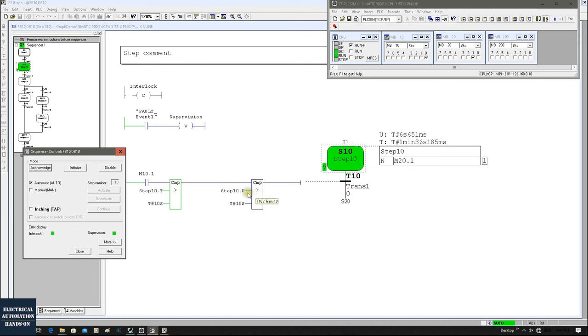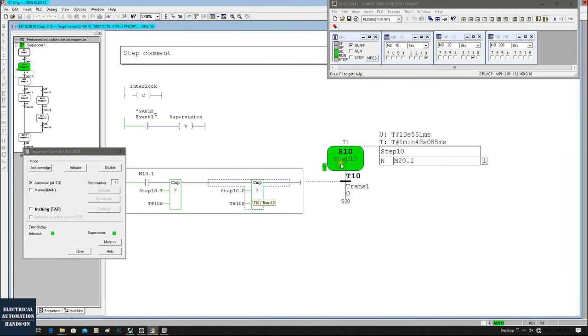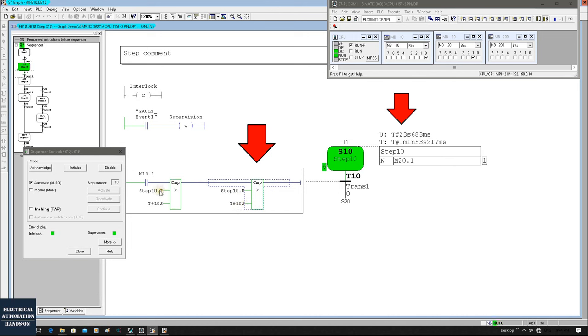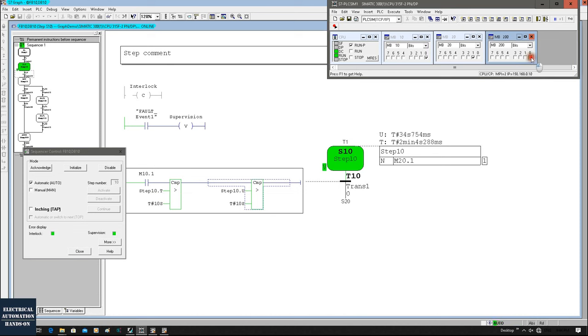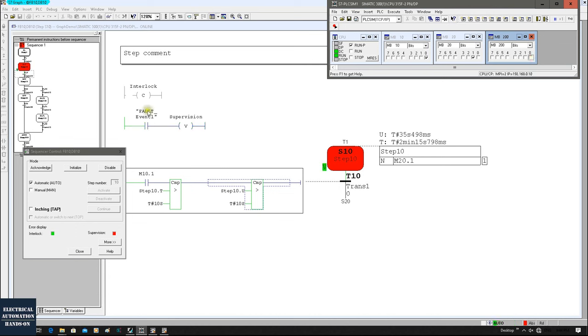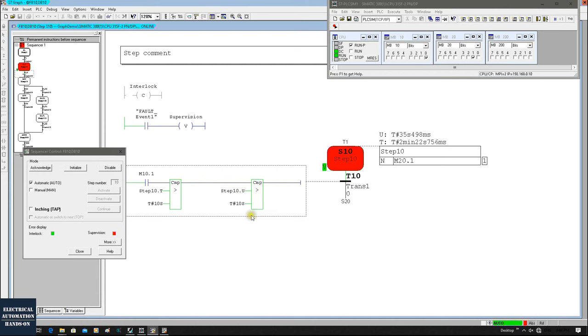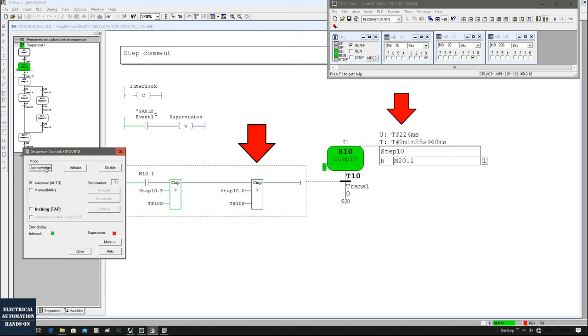After the fault clears, clicking Acknowledge turns the step green. At the same time, this brings up the next topic: the dot T and dot U timers. Once I acknowledge, the dot U timer will reset and recount the 10 seconds, but the dot T was already at 10 seconds. So once the step has run 10 seconds, dot T doesn't care anymore, but dot U — if any disturbance is triggered and then cleared — will recount the timer again after acknowledgment. This is the difference between dot T and dot U.